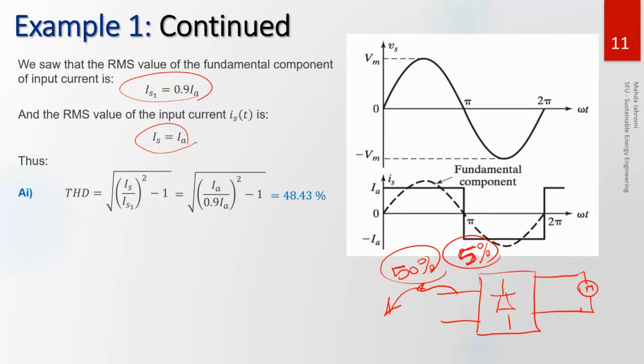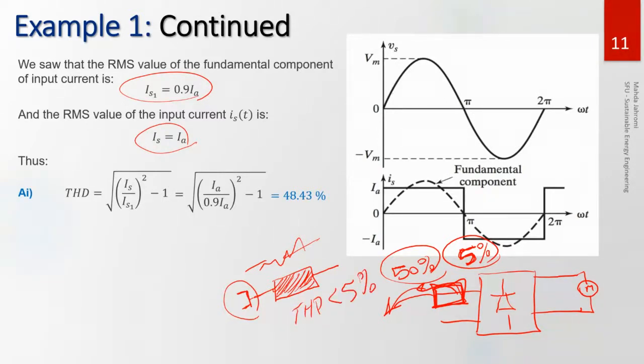So what that means is that somehow you have to have a filter here. You can't just plug this into the wall. You have to put a filter. And these filters, sometimes you see them in some devices. You see these cylinders on the wire, on the plug. The cylinders are the filters that filter the harmonics before you plug, for example, the DVD player or the home theater into the wall. That's to bring down the THD to less than 5%, which is what is required by the code.